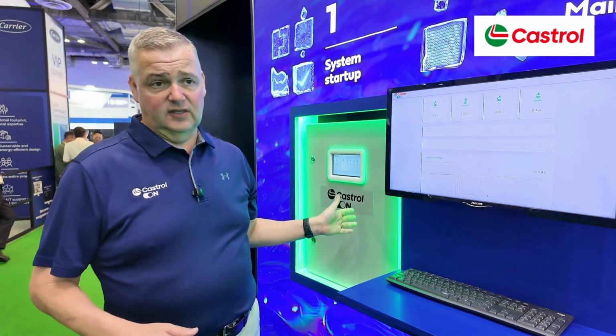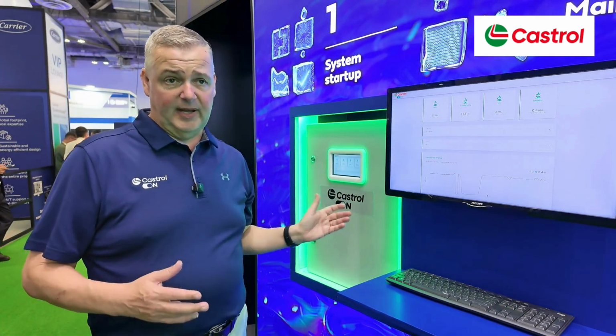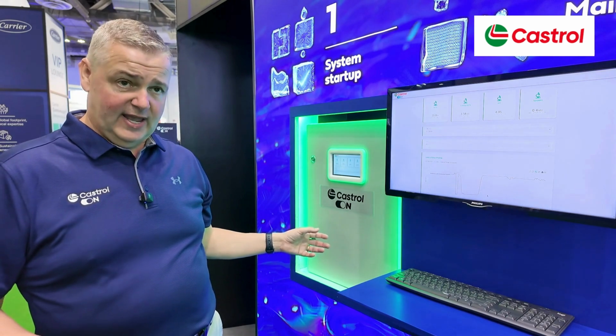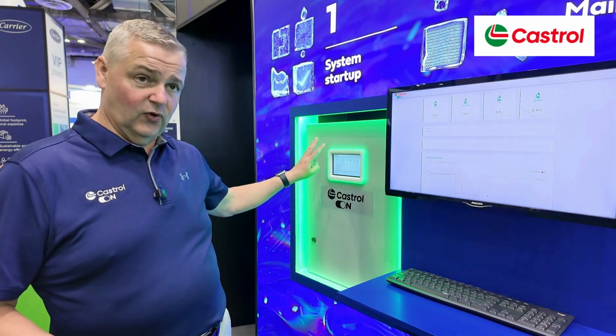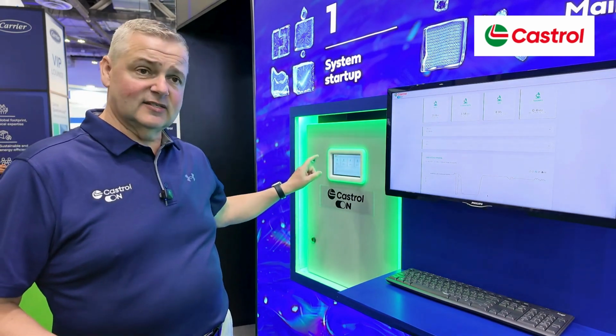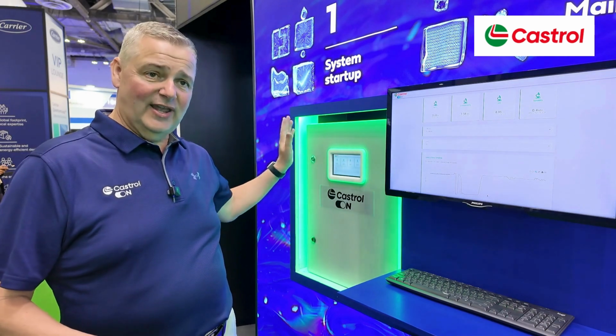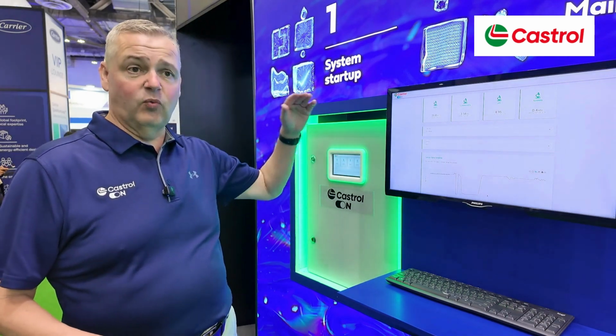In terms of the way it actually works, the unit sits on the return circuit on a bypass. It takes the fluid into the unit, it goes over the 4 sensors, it takes 10 readings, and that aggregates and then displays it. That repeats every 10 minutes. We can do it more frequently, but it probably doesn't make sense to do so.